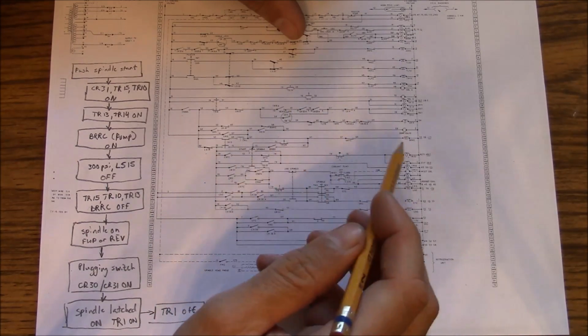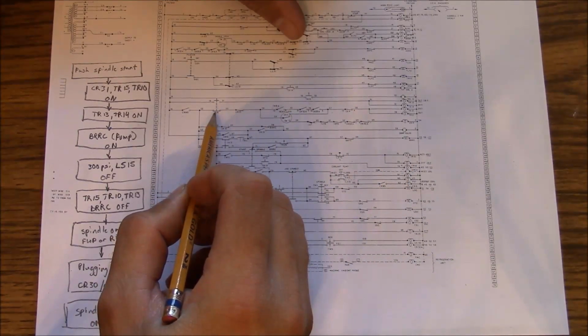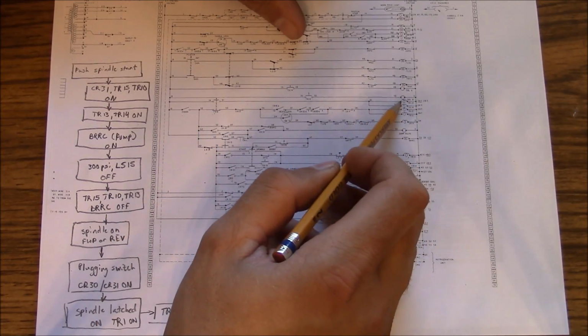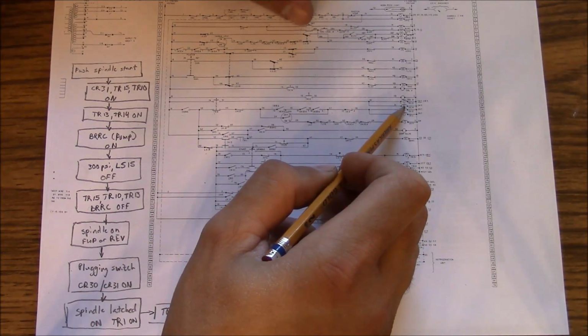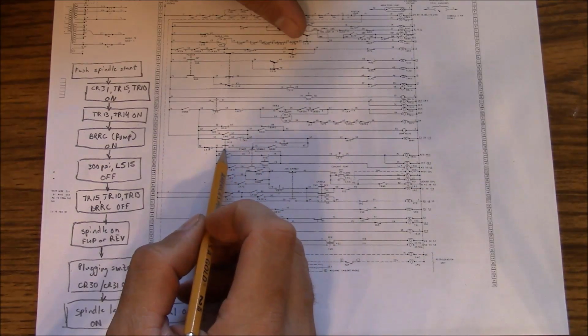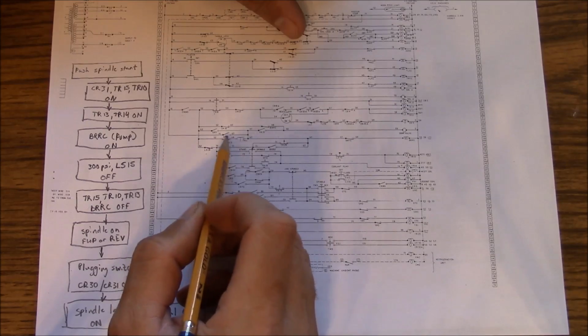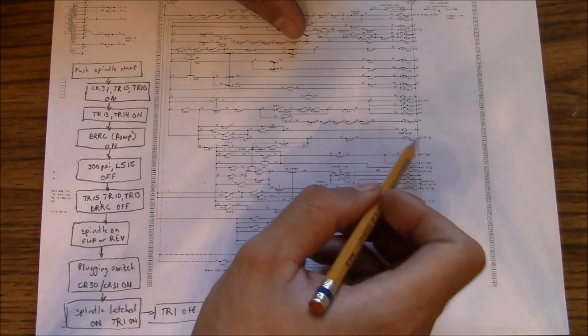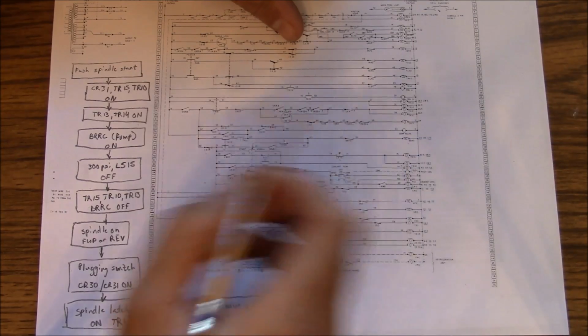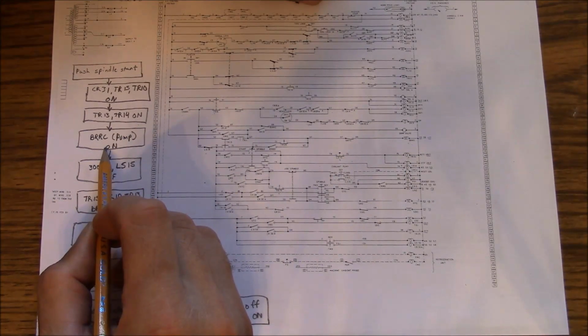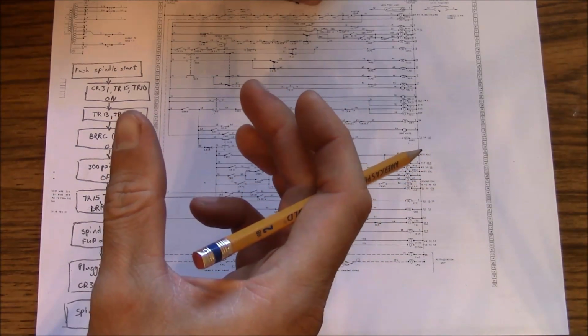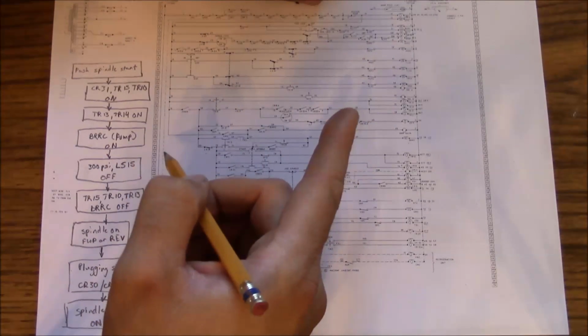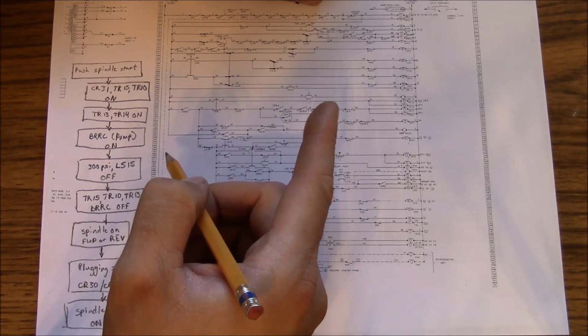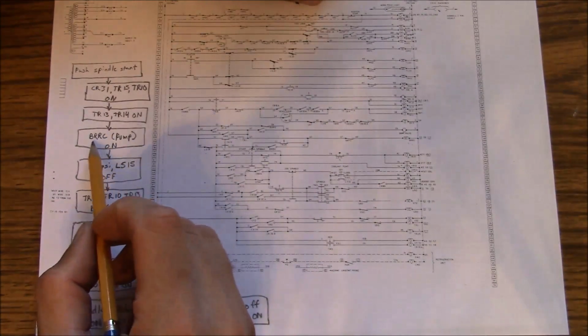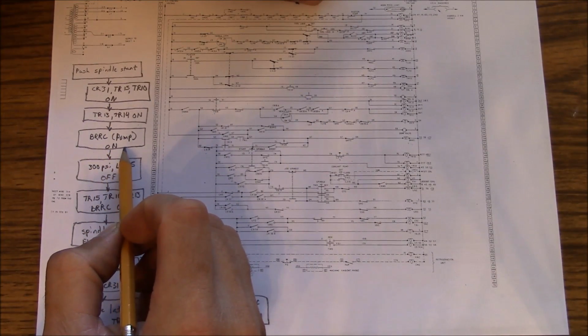Now, once TR10 timer relay starts, that's right here, it's going to allow timer 13 and 14 to start. Once timer relay 13 starts, it comes down here and switches this on, and it turns on this BRRC coil. So BRRC is a pump, and this DeVlieg has a preselect gearbox, so that means you can turn the dial to whatever gear you want, and then when you push the spindle start button, the machine automatically switches the gear for you through hydraulics. So this BRRC is the pump that shifts the gear.